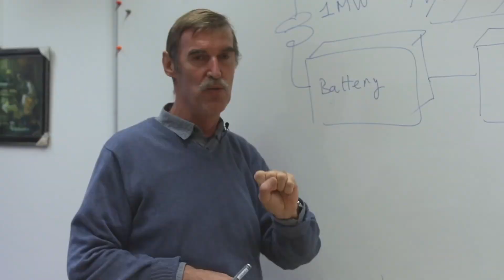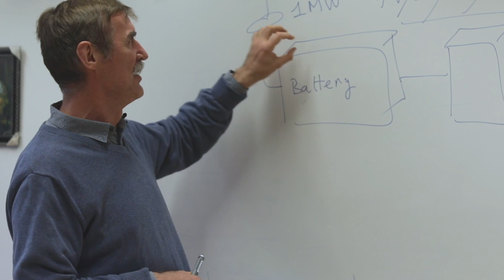With the Commelec real-time software, we can adjust in real time the power consumed by the EV, such that the total consumed power of the building and the EV does not exceed the rating of the transformer once we subtract what the PVs will do. The achievement of the control goals is done by satisfying the feasibility constraints of the local grid, using either control framework that we are implementing.